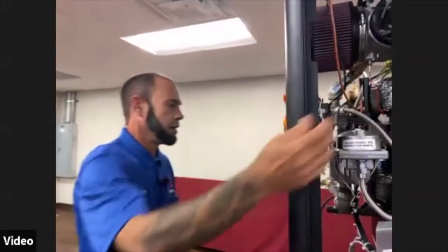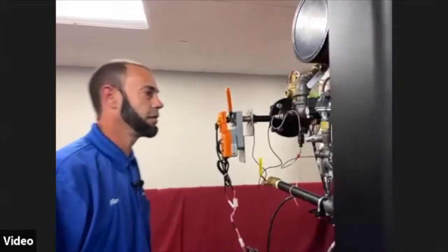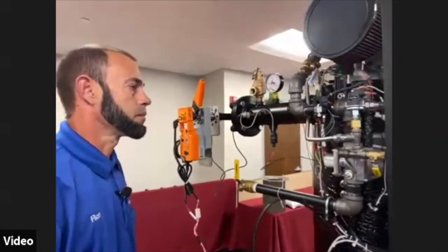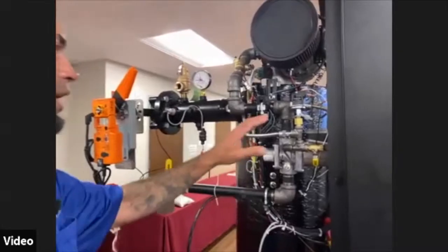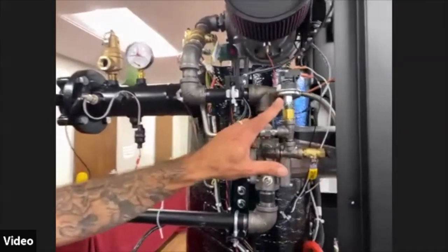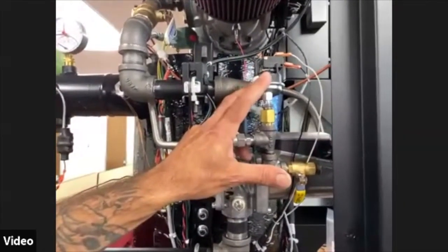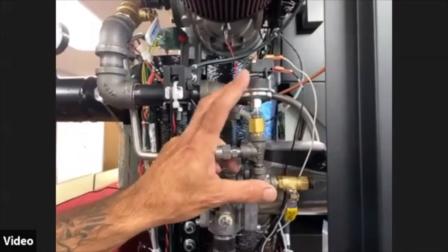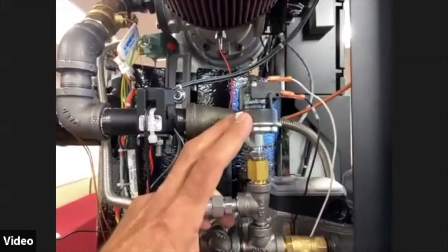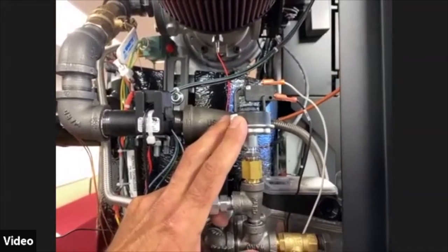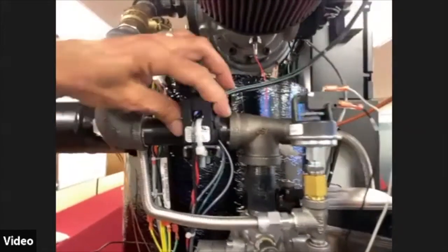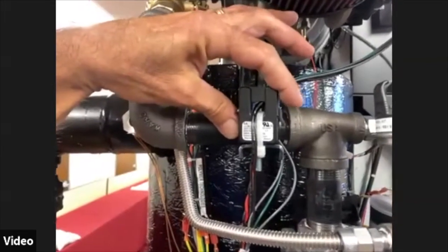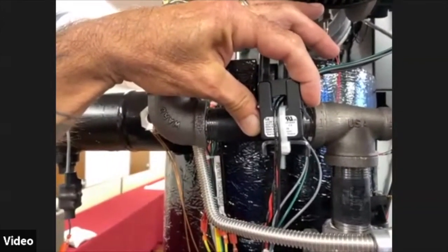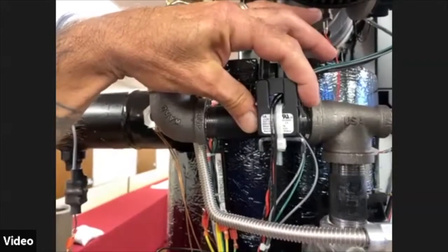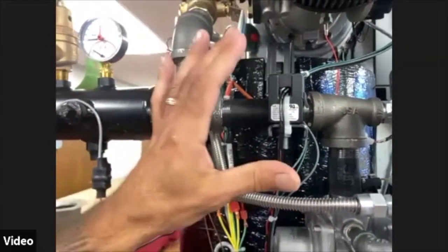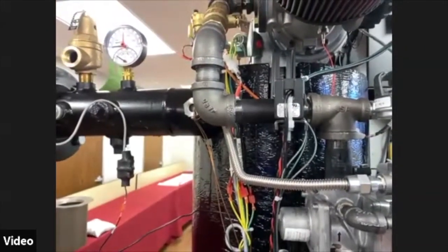Coming around to the side of the boiler, this would be the left side of the boiler. Again, you can get a little bit better look at that gas pressure switch. Some of these, depending on the model, will be automatic or manual reset. These happen to be automatic resets on the 1 million. This would be our current sensor, which is sensing spark. If we don't sense spark, obviously we'll go into a fault as well. It doesn't necessarily mean the current sensor is bad. There could be something else going on.